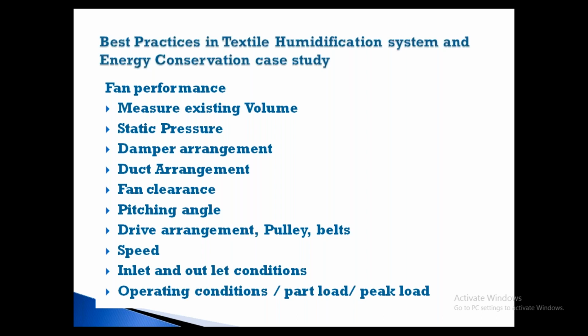From the maintenance point of view, people think that okay, if the gap is more, there is no problem, but there is more gap. Even in some places we can see in the axial flow fan, between impeller and casing, even your hand will go inside. That much gap is there. That means you are totally wasting the power. Only the impeller will be rotating.